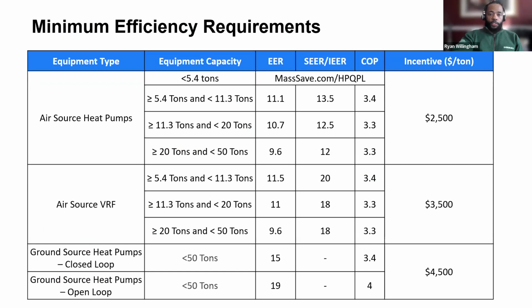Here are the minimum efficiency requirements. So for less than 5.4 tons, we do have a qualified products list located at that URL, and that aligns with the residential product list as well. So it's all one qualified product list. And then for the larger air source units as well as the air source VRFs and ground source systems, those are the minimum efficiency requirements. And I believe Lauren will be sharing these slides, but these are also available on masssave.com.